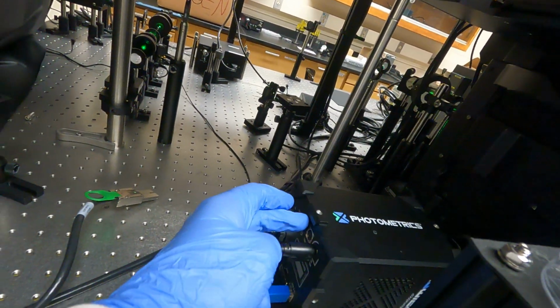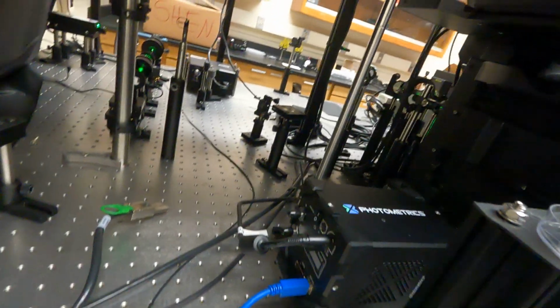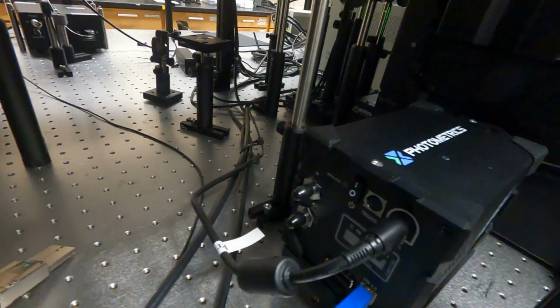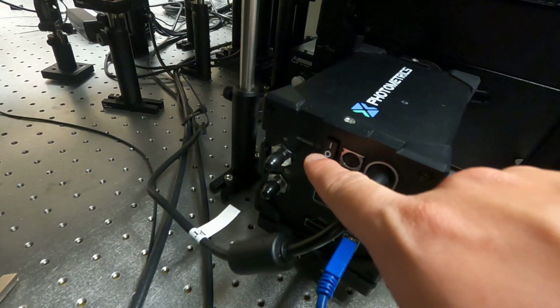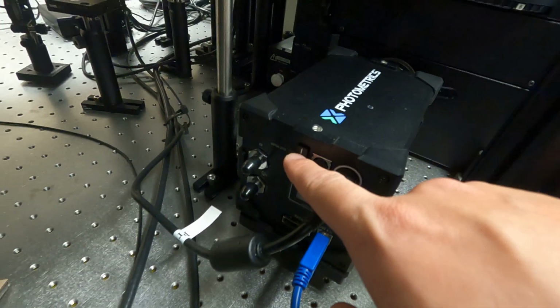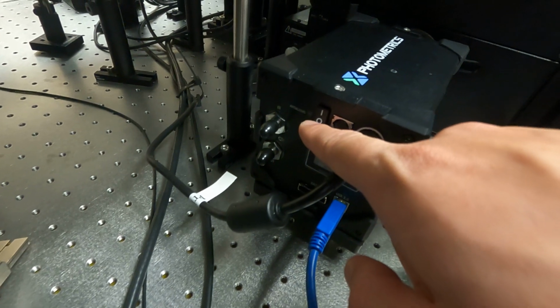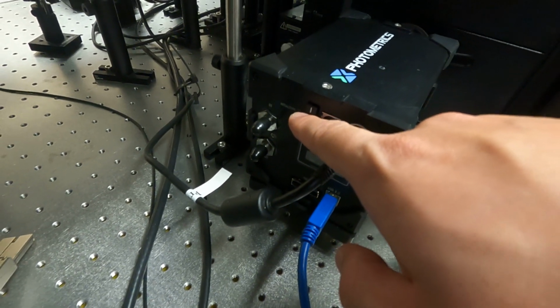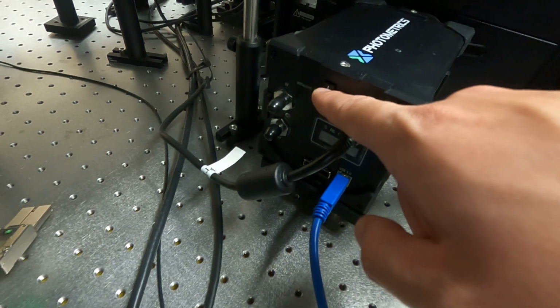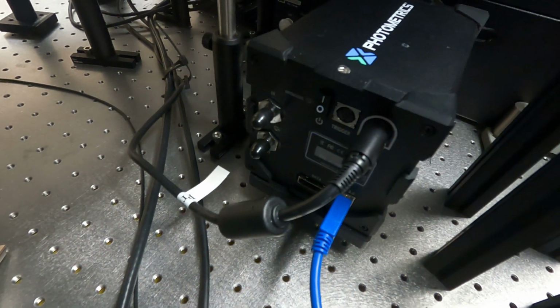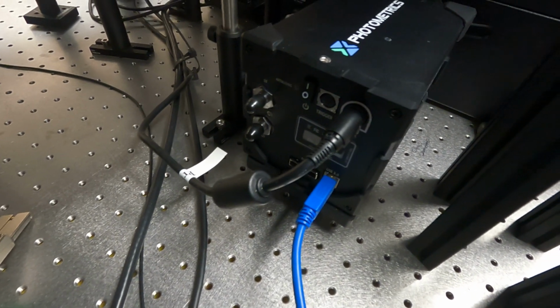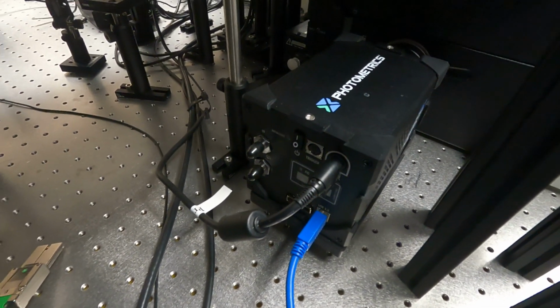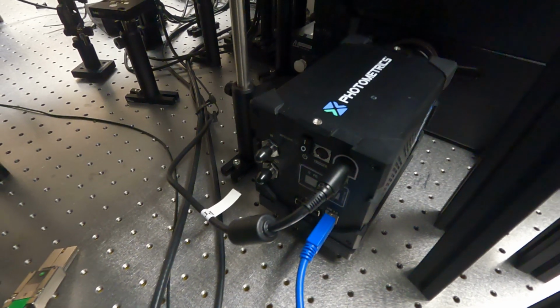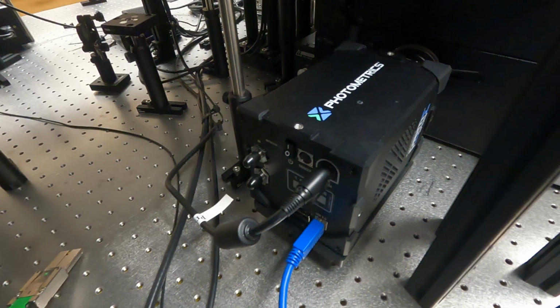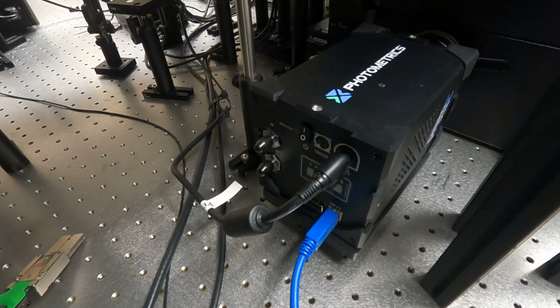Okay, the power supply is located here at the back of the camera. Once you press this button, you hear the fan noise and also a blinking light right next to this power button. This indicates the heating process. We will wait until the flashing light turns itself off. That means the self-checking process is completed. We have to do this, or otherwise the CellSense program on the computer will not recognize the camera. So we'll have to wait until the blinking light stops, and then we can proceed.